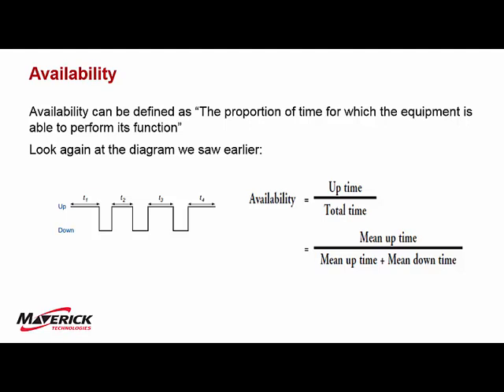Another term is availability. Availability is how often is it working. It's the proportion of time that the equipment's able to perform its function. So it's all of the T's added up over all of the time together. And you may wonder why are some of these downtimes longer than others? How long does it take to repair something that fails? Well, part of the problem is you may not realize it failed. And availability is not the same thing as reliability. Reliability is strictly mean time between failure. How long will it run? If you have a cheap pump, but that pump is pumping every day and you'll know as soon as it's down and you'll fix it quickly, its availability is going to be high because it will run, you'll break it, you'll get it right back running again. But its reliability might be kind of crappy. So they're not exactly the same thing.